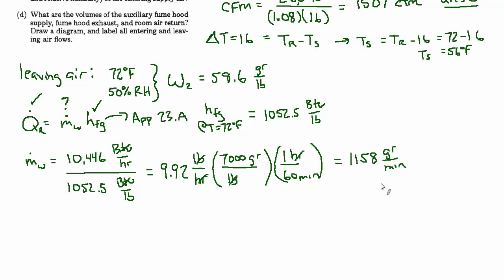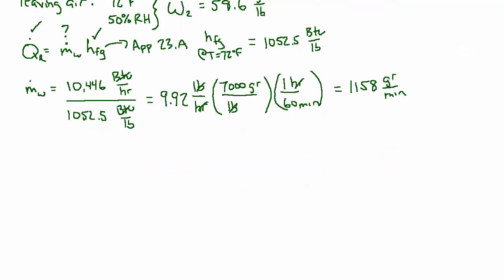So that's how much water vapor is being added to the air on a continuous basis. And now we can use this formula that says the mass flow rate of water equals the mass flow rate of air times the delta of the humidity ratios of the two streams. So we just found the mass flow rate of water.